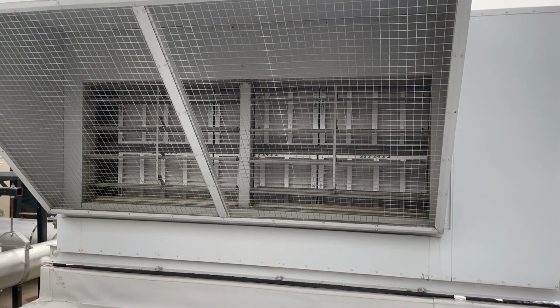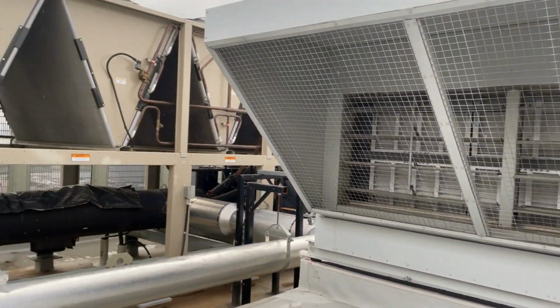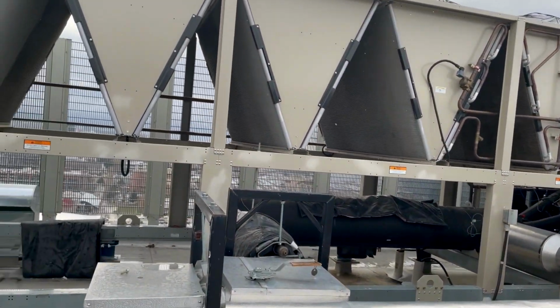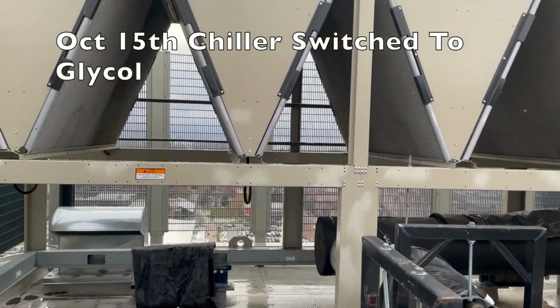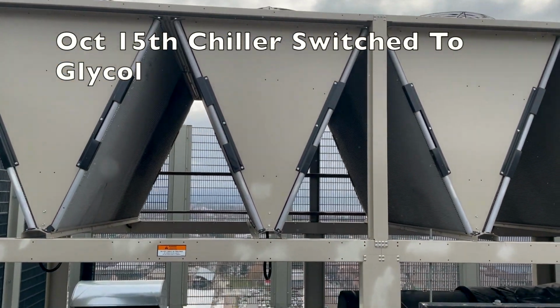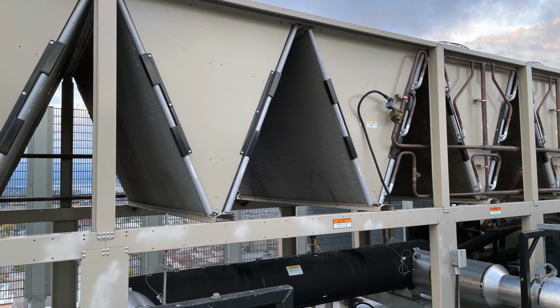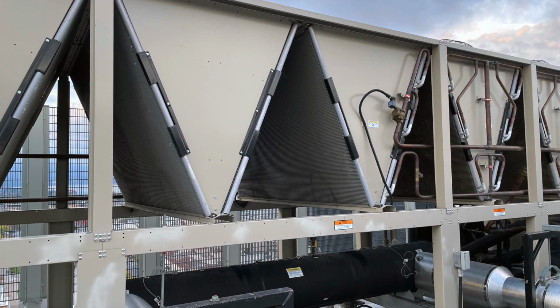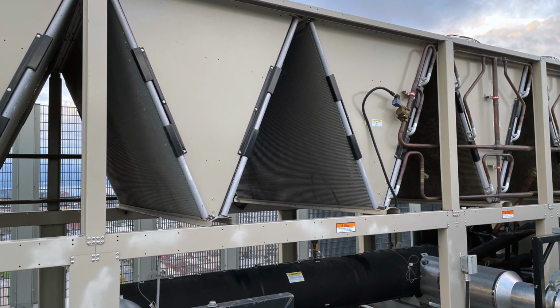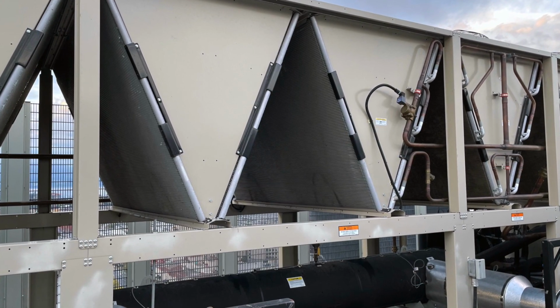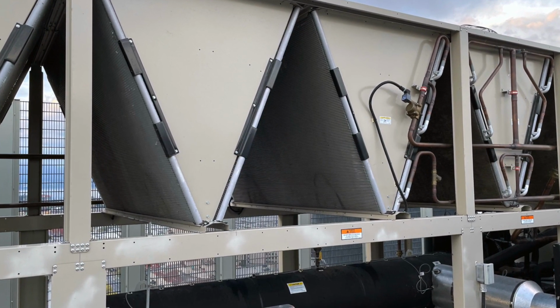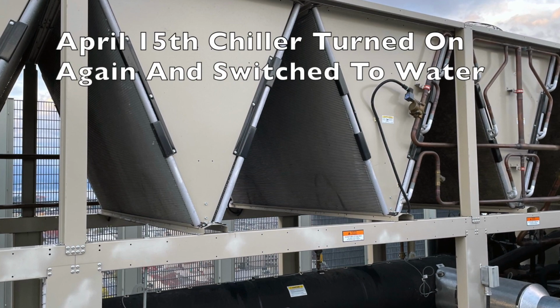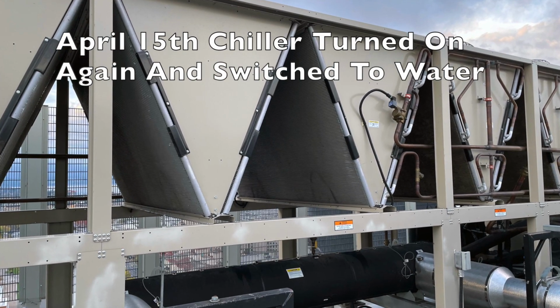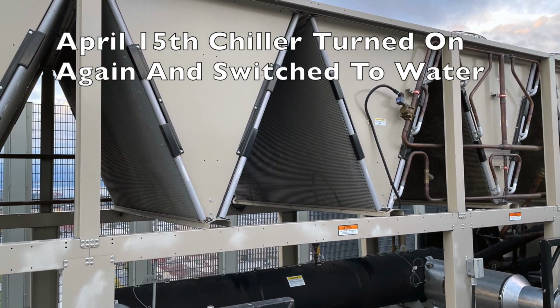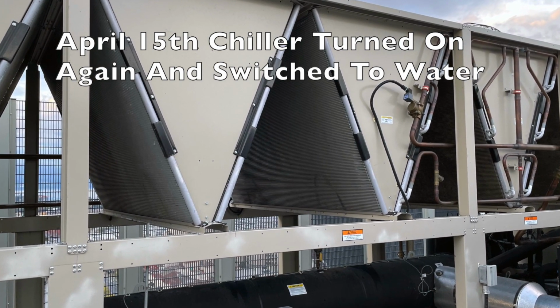Now, over on the other side, these are our chillers. The chillers were shut down on October the 15th. At the same time, the chillers are filled with glycol so there's no freezing, since they're on the outside of the building. Then on April the 15th, the chillers are turned on again and filled with water, because the thermal efficiency of water is much better than glycol.